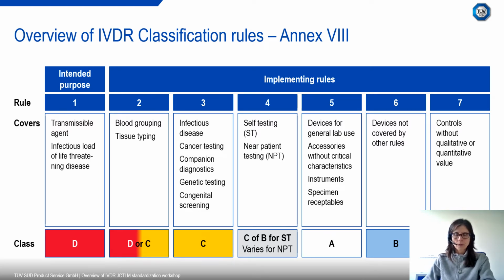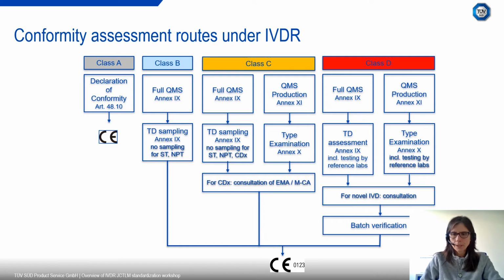The advantage of this system compared to the system used in the directive is that it is more complex, but it provides more flexibility when new devices or new markers become available and need to be placed on the market with an appropriate conformity. Conformity assessment routes under the IVDR depend on the risk class of the device. For class A, notified body involvement is not required, so conformity with regulation requirements is self-declared by the manufacturer. For the other risk classes, a notified body is involved.